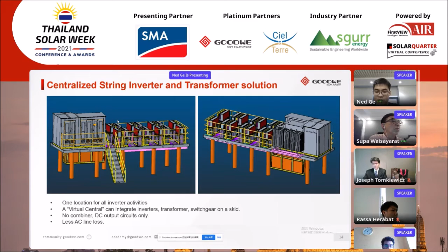But the longer DC cable design will slightly raise the cost of the system, but what we gain more from this is an easier O&M plan on a large site, and you are saving installation later as well. This has been done in a large application right now in Qinghai province, China. We can also install the inverter on an individual skid and build the frame close to the step-up transformer pad. Besides, the virtual central solution, compared to a central inverter, will have lower cost as it does not include any DC combiner box, and it also makes up for the disadvantage of distributed string inverters' longer AC conductor. This also lowers the AC conductor cost, with lower AC line loss. So we are balancing the system cost by using this solution to lower your LCOE.